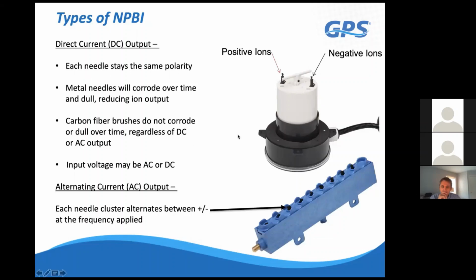But you have direct current systems and you have alternating current systems. Direct current systems will have the electrode stay the same polarity 24/7. So what that means is, as particles are moving through the air, particles that are oppositely charged are going to hit that electrode and stick. So over time, you're going to see the electrode start getting dirty. And for that reason, we've developed these auto cleaning systems. So every 3 days out of the box, this wiper blade turns on and rotates, and it cleans these brushes off automatically. So there's no maintenance to the systems, and there are no replacement parts with our systems.